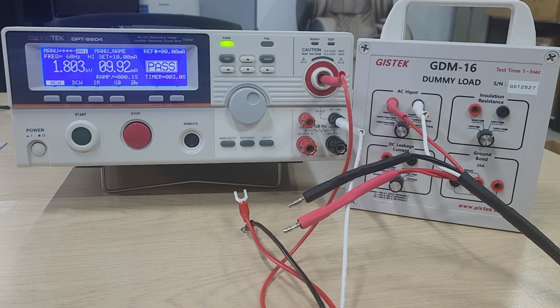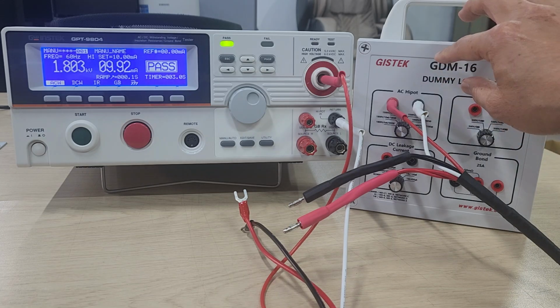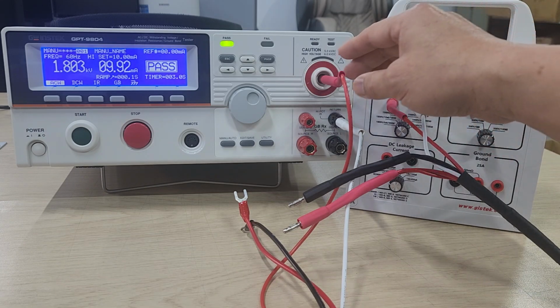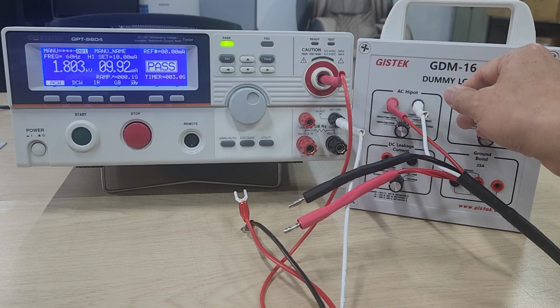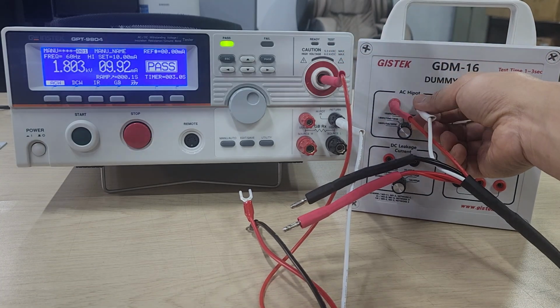The second method is the DC insulation resistance tester. Connect the DC insulation resistance test terminal of the DC insulation resistance tester and the dummy load with a cable. The DC insulation test is the same method as the AC withstanding voltage tester, so move this cable away and change to the dummy load DC insulation resistance terminal.